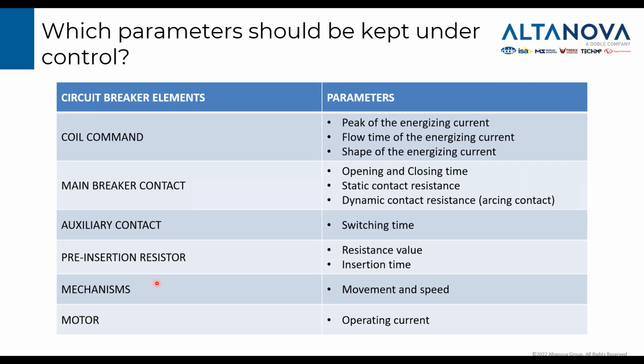What parameters should be kept under control? We have to control the status of the coil commands. The parameters that represent the status of these coil commands are the peak of the energizing current, which, if it is too high or too low, represents an issue; the flow time of the energizing current, which, if there is a problem, may be taking too long; and the shape of the energizing current, which also gives some information about, for example, the mechanisms. We will see this concept in more detail in one slide.